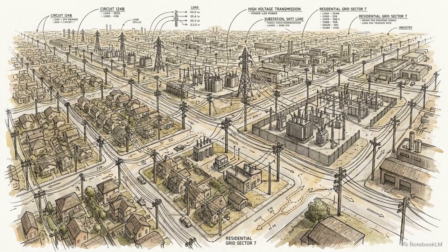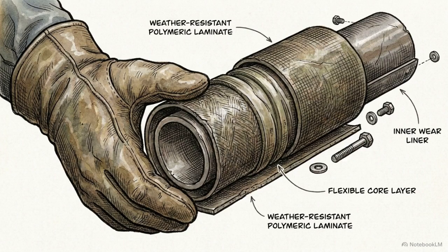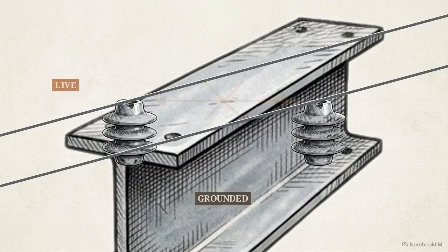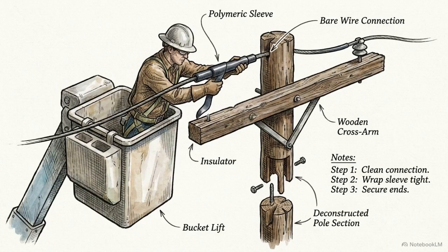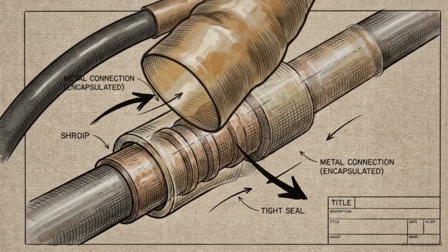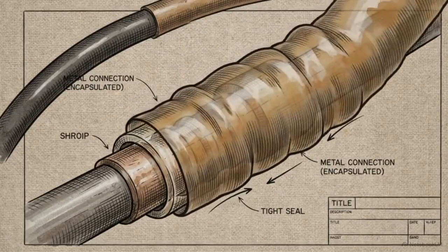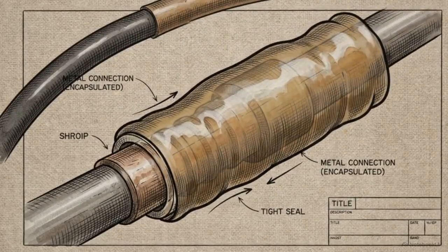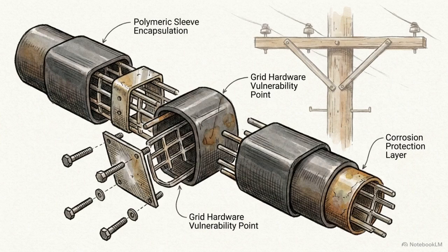The constraints of fixing this are brutal. We cannot shrink the wingspans of migrating eagles, and rebuilding millions of miles of existing grid to widen the structural gaps would cost trillions. The viable solution relies on advanced material science. Instead of moving the wires further apart, engineers can insulate the exact bare metal vulnerabilities on the existing hardware. Utility crews deploy specialized, UV-stable polymeric heat shrink tubing and wraparound covers. Clamping down over the exposed connections, these materials form a weather-resistant dielectric barrier that prevents current from reaching the air. By applying these targeted materials to specific hardware points, we can adapt a rigid human grid to the unpredictable shape of the animals living around it.